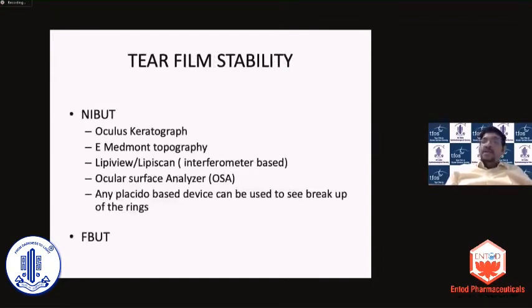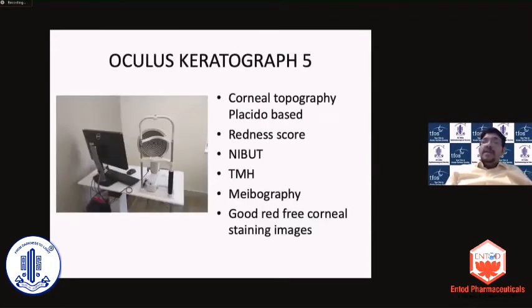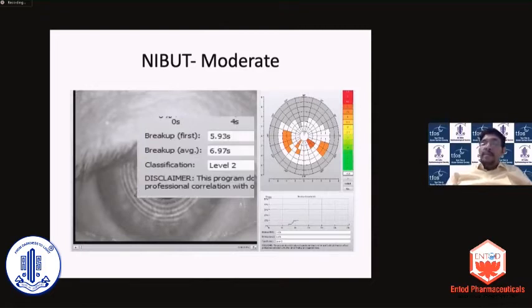The first homeostasis test is tear film stability. You have two ways of measuring it: a non-invasive method and the invasive fluorescein breakup time. It is preferable to use the non-invasive because fluorescein will alter tear film stability. However, a non-invasive test is expensive. The normal cutoff value for non-invasive TBUT is around 10 seconds, with about 80% sensitivity and specificity. Machines like the Oculus Keratograph can give you non-invasive breakup time and also provide meibography and redness scores, showing where the tear is breaking up faster along with average first and mean breakup time.